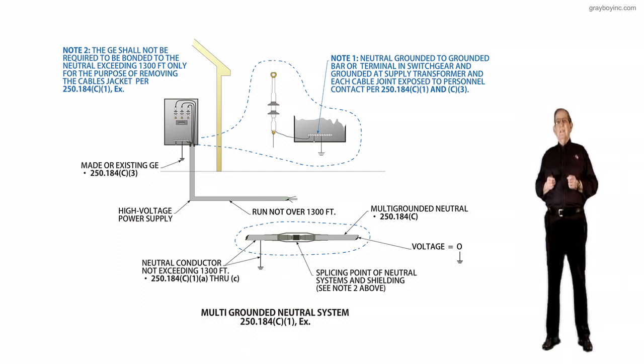So now, reviewing, the first thing that we need to call out here is the high voltage power supply. We know it's high voltage, it's over 1,000 volts. And we know that it's made or existing grounding electrode, as you see in the panel there, and it's not over 1,300 foot, the call out that has the arrow to the cable. The third thing is the neutral conductor, this little call out, neutral conductor not exceeding 1,300 feet in accordance with 250.184(C)(1)(a) through (c) there.